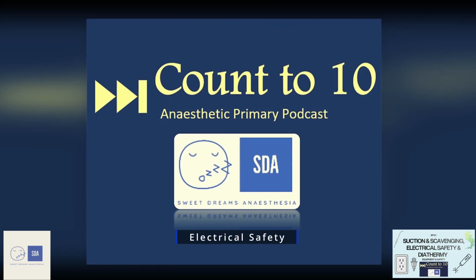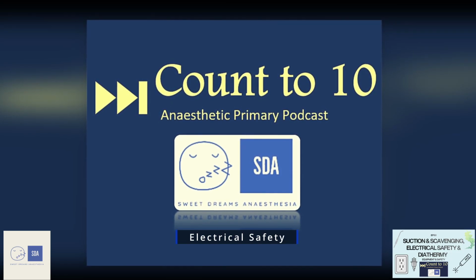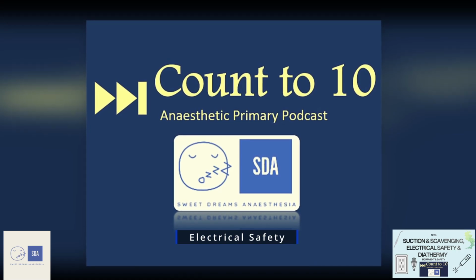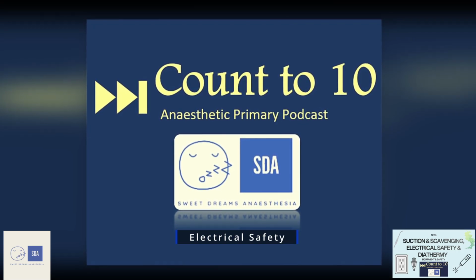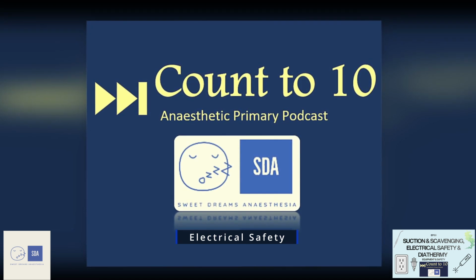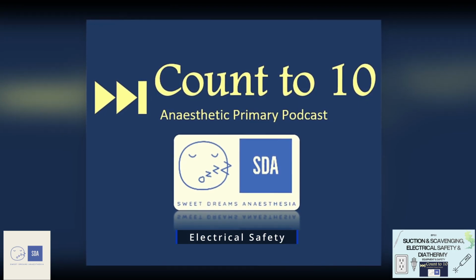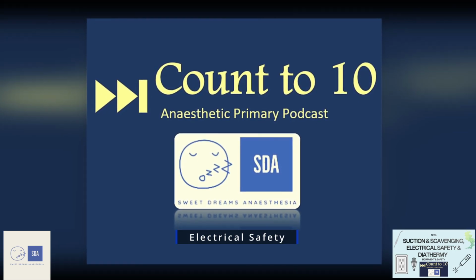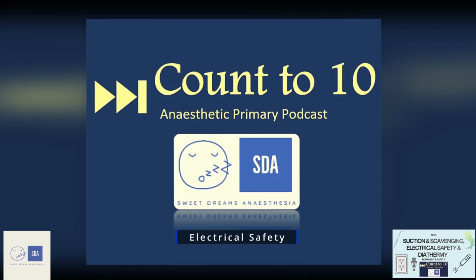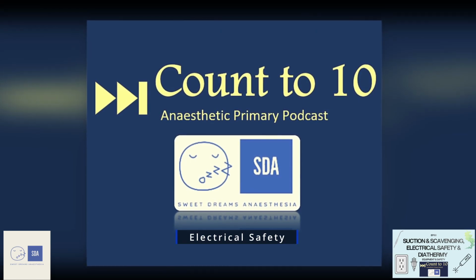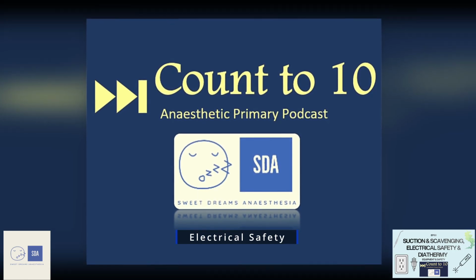Starting off with residual current devices, or RCDs, these are monitors that balance the current between the live wire and the neutral wire. And if there is some current leakage to the earth wire, this imbalance causes the device to trip and cut power. They're really smart devices and they're used outside of the hospital system as well, and they can detect a current leak from anywhere between 5 to 10 milliamps. And once that current leak is detected, they'll cut power supply within 40 milliseconds.